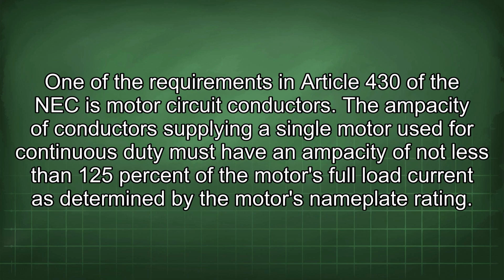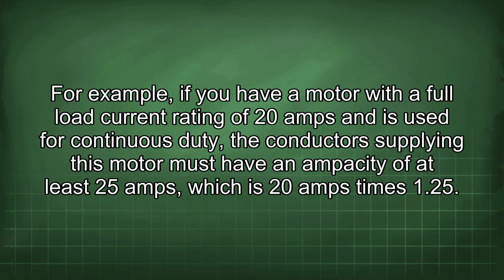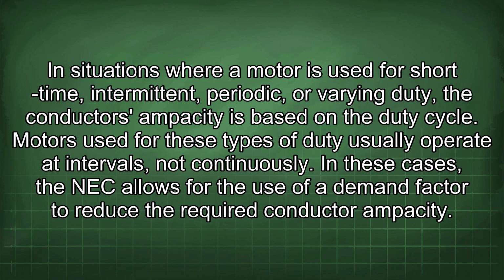This code provides standards for electrical safety and proper installation methods. One of the requirements in Article 430 of the NEC is motor circuit conductors. The ampacity of conductors supplying a single motor used for continuous duty must have an ampacity of not less than 125% of the motor's full load current as determined by the motor's nameplate rating. For example, if you have a motor with a full load current rating of 20 amps and is used for continuous duty, the conductors supplying this motor must have an ampacity of at least 25 amps, which is 20 amps times 1.25.